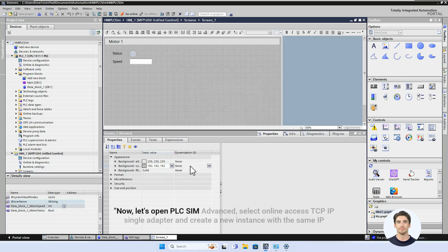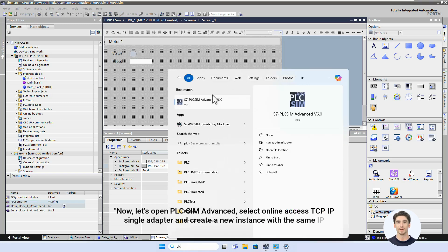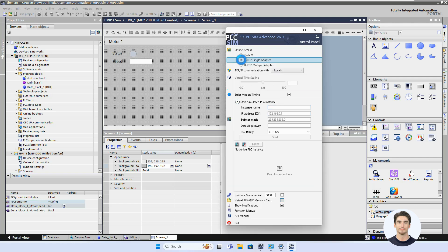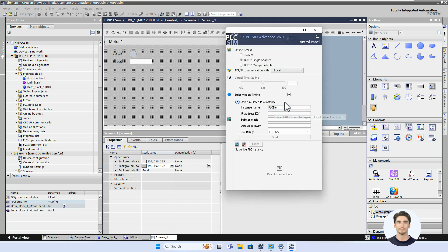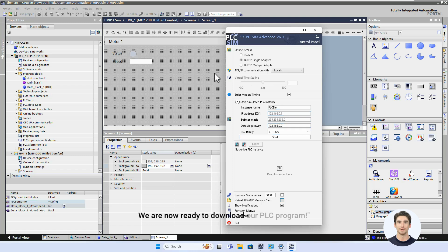Now let's open PLC SIM Advanced, select Online Access TCP/IP Single Adapter, and create a new instance with the same IP address as our PLC. Select PLC SIM Virtual Ethernet Adapter. We are now ready to download our PLC program.